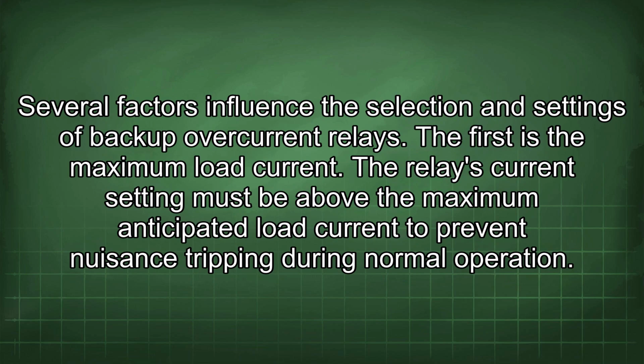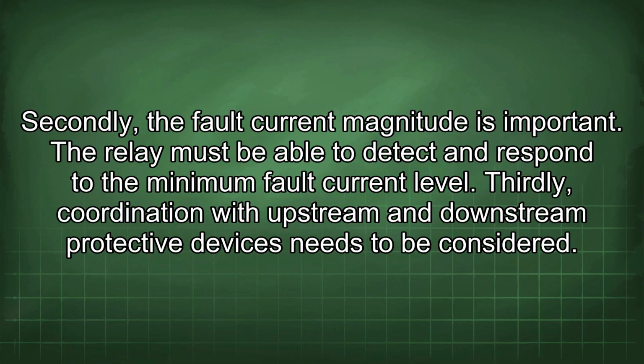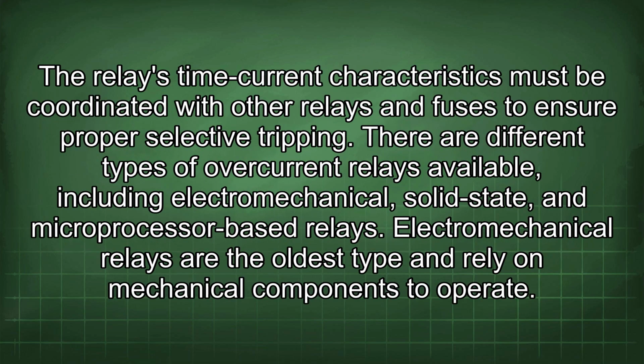Several factors influence the selection and settings of backup overcurrent relays. The first is the maximum load current. The relay's current setting must be above the maximum anticipated load current to prevent nuisance tripping during normal operation. Secondly, the fault current magnitude is important. The relay must be able to detect and respond to the minimum fault current level. Thirdly, coordination with upstream and downstream protective devices needs to be considered. The relay's time current characteristics must be coordinated with other relays and fuses to ensure proper selective tripping.